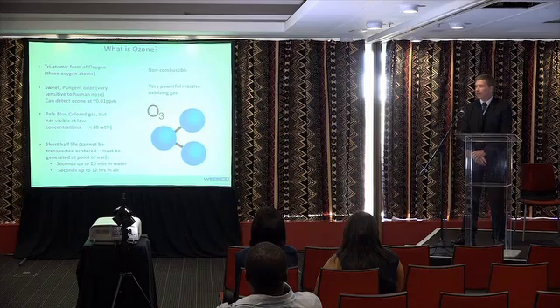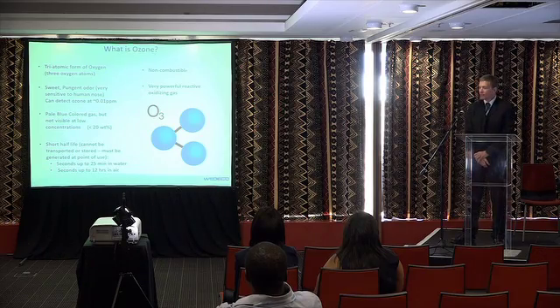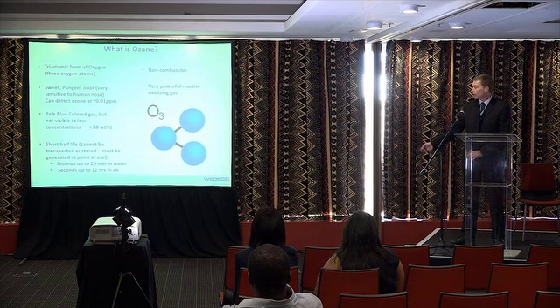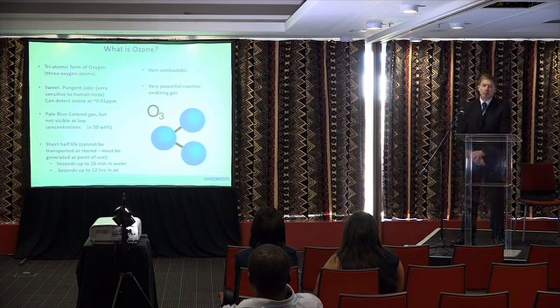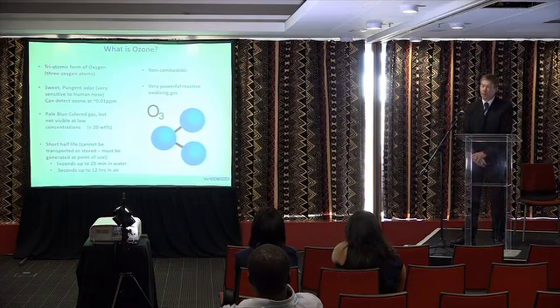It's highly reactive, with a nice blue color that you won't really see unless you're looking inside the generator, and a very distinctive smell — once you've smelled ozone, you can pick it up at parts-per-billion levels. It has a very short half-life, and the beauty of this is that there is no secondary pollution. Ozone breaks down back into oxygen, which is a benefit to the environment — about 25 minutes in water and up to 12 hours in clean air.